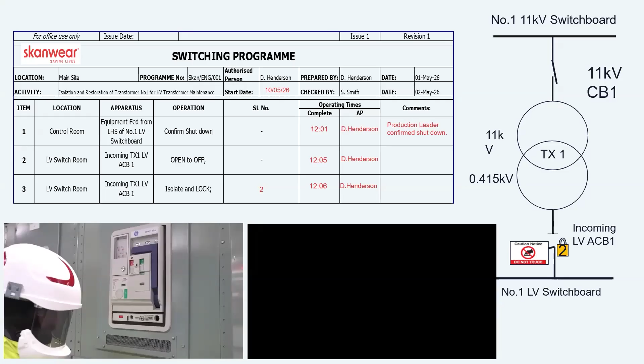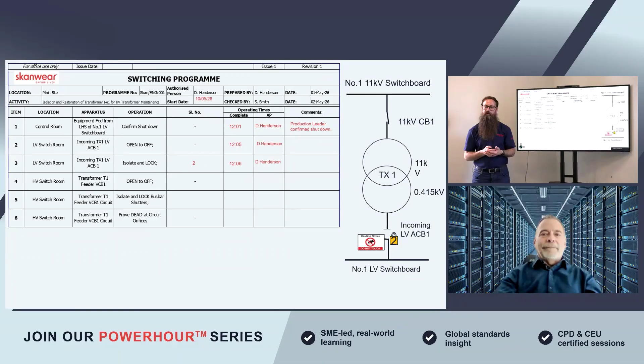We're now going to go into the next one. We've done steps 1 to 3. We're now going to go to the HV switch room, identify the equipment as transformer T1, feeder VCB1, and we're going to open to off. So visual verification, we're in the right place, push that button, and then we've checked the indication to show that it's off. I'll then update my switching plan with the time of operation and who did it.